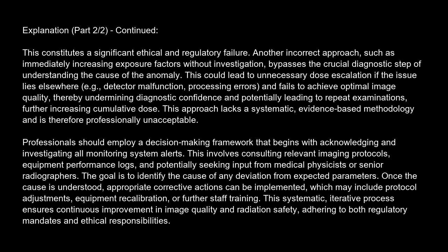This approach lacks a systematic, evidence-based methodology and is therefore professionally unacceptable. Professionals should employ a decision-making framework that begins with acknowledging and investigating all monitoring system alerts. This involves consulting relevant imaging protocols, equipment performance logs, and potentially seeking input from medical physicists or senior radiographers. The goal is to identify the cause of any deviation from expected parameters.